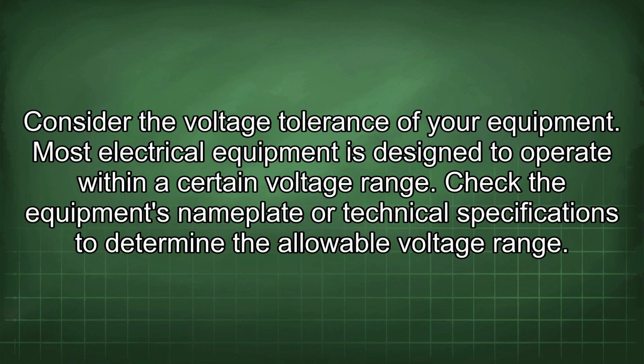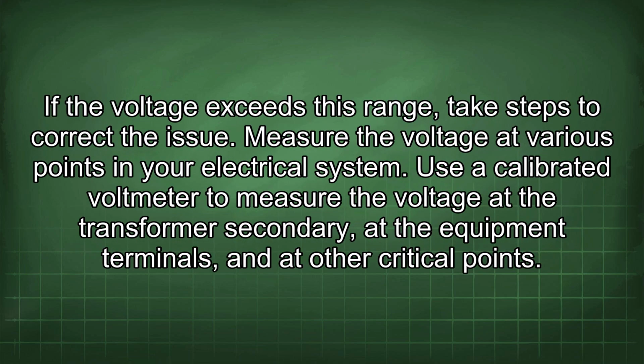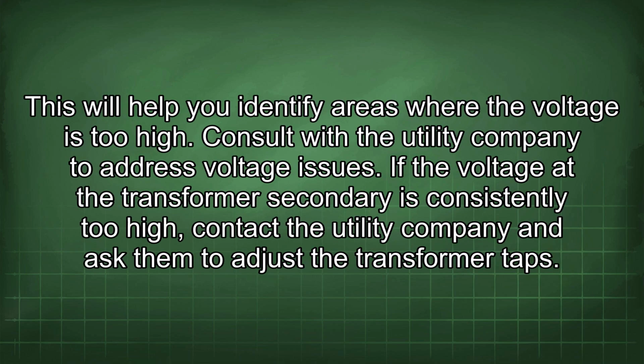Consider the voltage tolerance of your equipment. Most electrical equipment is designed to operate within a certain voltage range. Check the equipment's nameplate or technical specifications to determine the allowable voltage range. If the voltage exceeds this range, take steps to correct the issue. Measure the voltage at various points in your electrical system. Use a calibrated voltmeter to measure the voltage at the transformer secondary, at the equipment terminals, and at other critical points. This will help you identify areas where the voltage is too high.